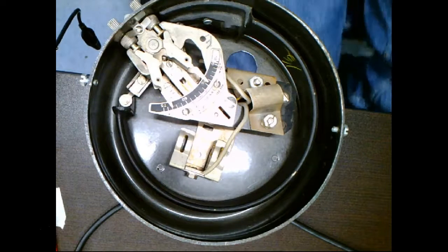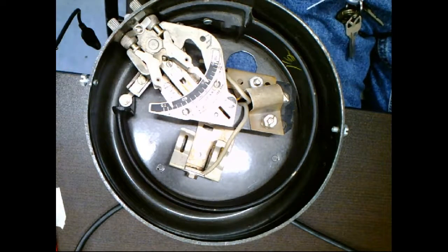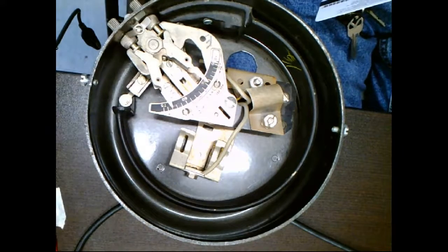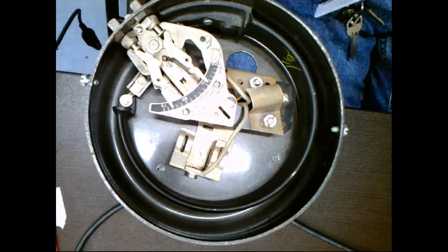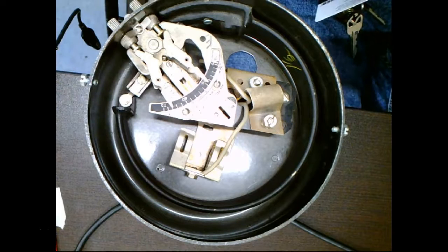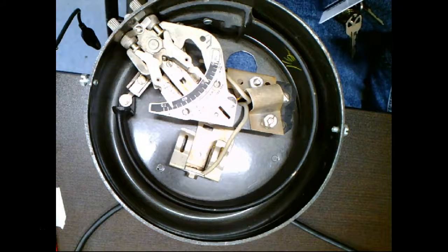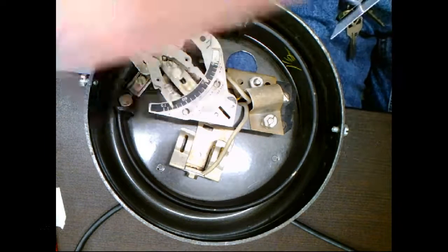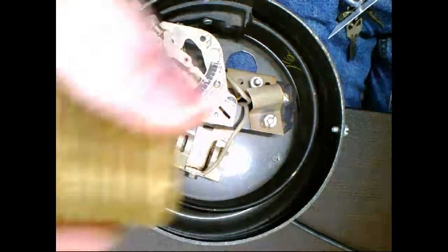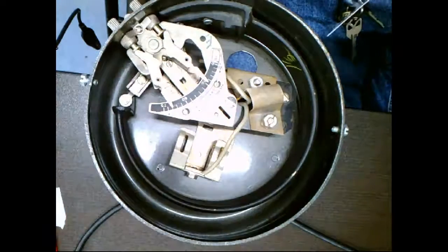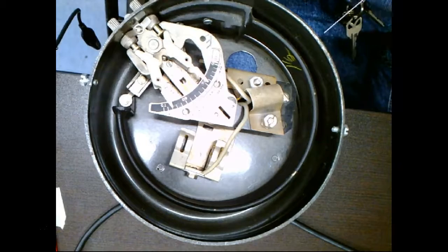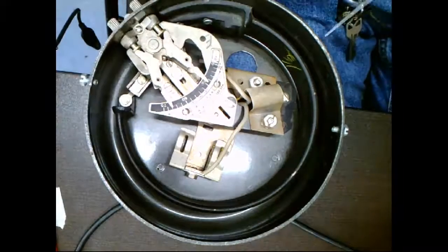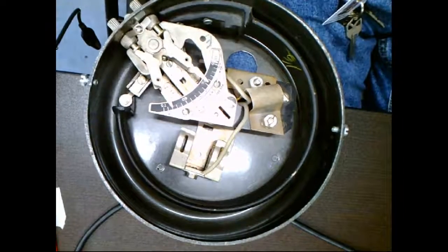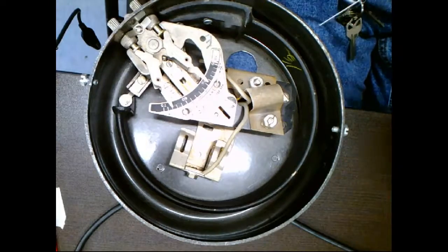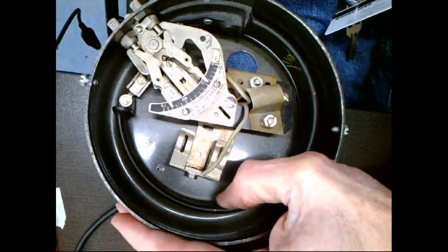It all depends - some we have solid state pressure switches that work on a piezoelectric principle, piezo resistance. What you're going to run into is the older the equipment is, the more likely you'll have stuff like this and not solid state equipment. Like this guy here, this has been around for as long as I can remember, even before Rich. This is called a Bourdon tube.